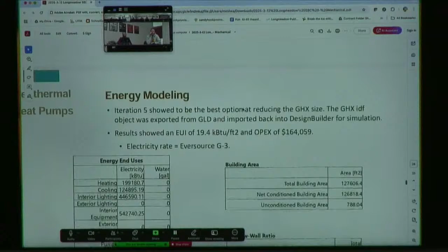All right, so going to this next one, I just want to talk a little bit more about this table, because the next one is a 50 borehole configuration. So if you go with the package that over-insulates and has the lower solar heat gain coefficient, which is iteration 16 there, you have a cooling imbalance of 17 times. And then the borehole field goes up to 50, and again, that is driven by this long-term heat accumulation in the ground. So then if you flip the scenario and go to more or less the least amount of insulation, the ASHRAE 16 baseline, you get really nice balancing on the ground, but then the borehole field has to go back up in size just to meet that first-year heating demand.